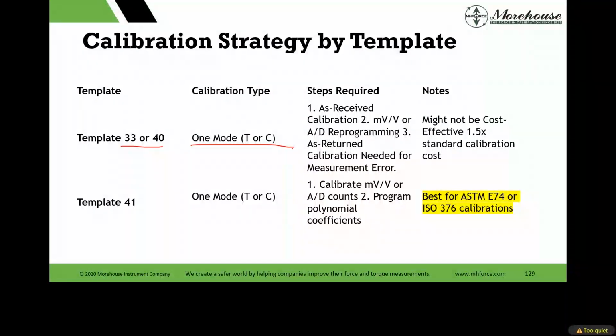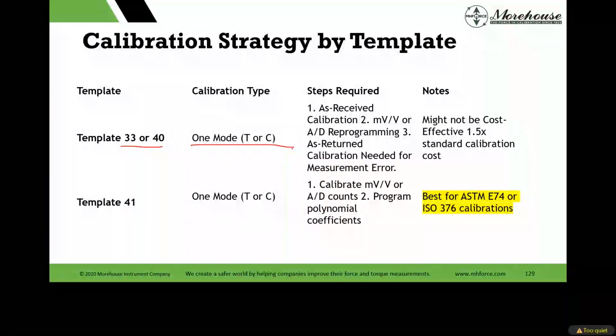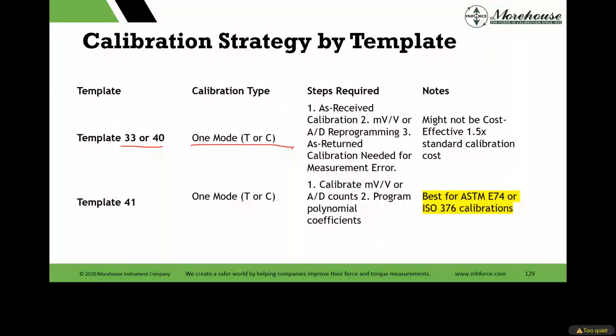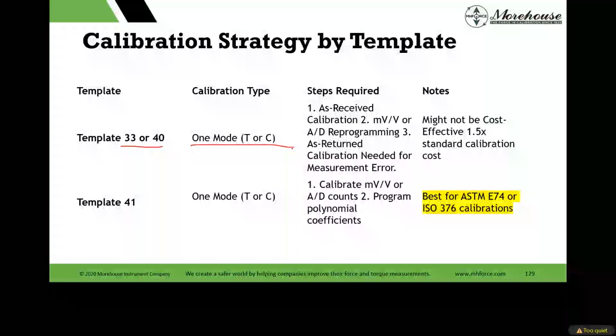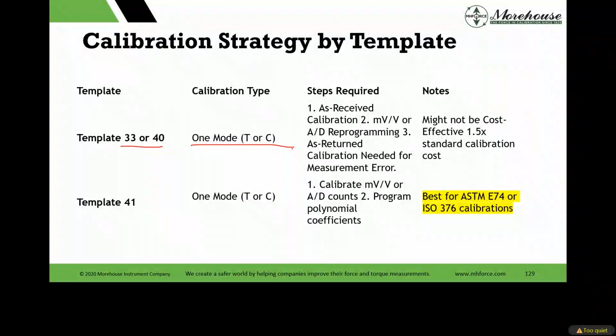There are special programs that the labs need to have. Some companies lock you out, meaning it's proprietary, and the writing of the chip. So when they lock you out, that effectively means that you sent your equipment to some lab to perform the cal. They're reporting out. You want it to read closer to nominal. You want 10,000 to read 10,000. So now you had an accredited cal. You need to send it back to the company that has the special software. And then since they're not accredited, then probably back to the lab that is accredited, if that's the whole scenario.